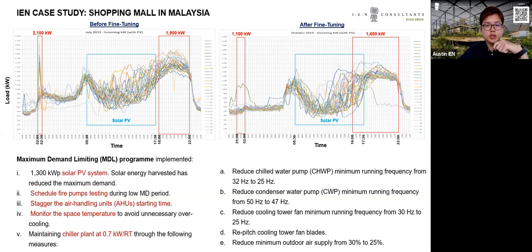We reduce the chilled water pump, the condenser water pump, and the cooling tower minimum running frequency. We repitch the cooling tower fan blades, and also reduce the minimum outdoor air supply from 30% to 25%, while still complying with ASHRAE standard.